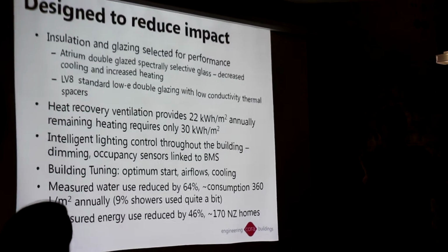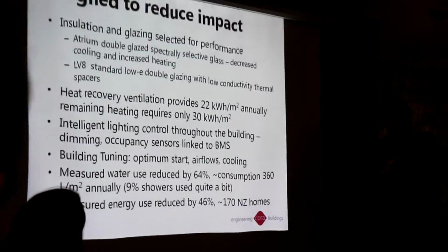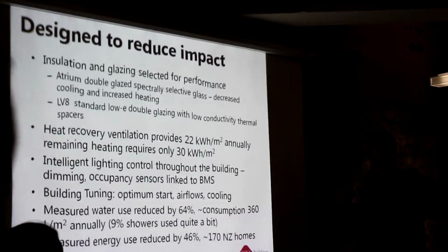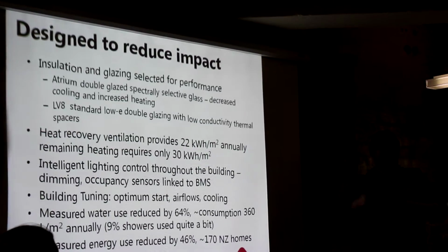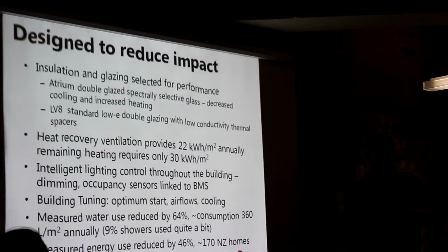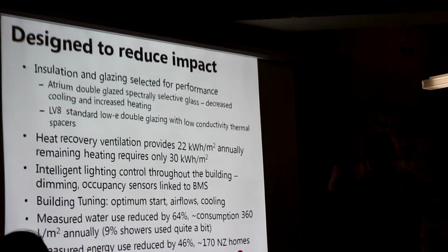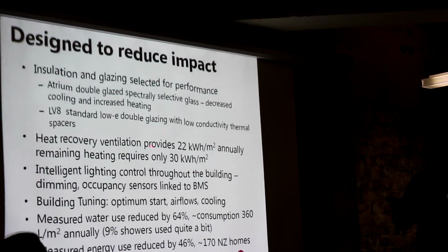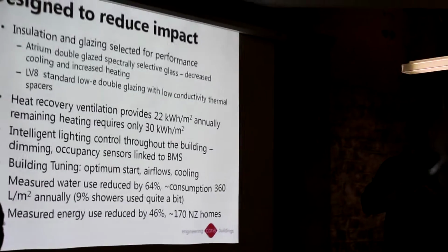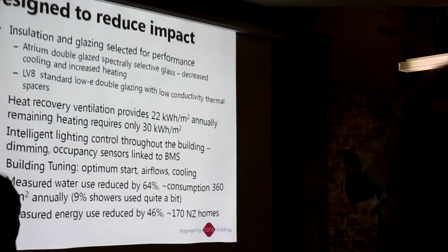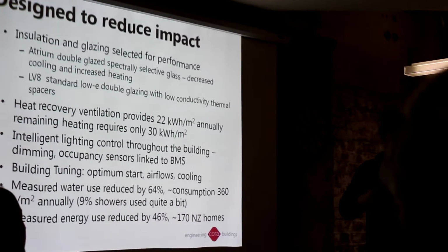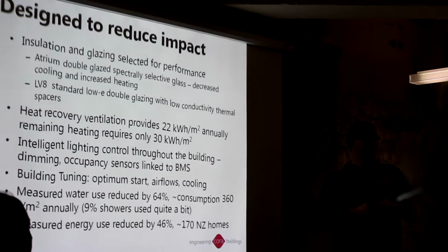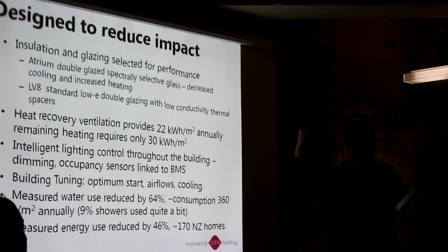When you're trying to design a low energy building, there's essentially two ways to think about energy flow through the building. Flow through the skin, which is either radiation or conduction, and then there's the intentional exchange of air. You don't want to breathe the same air inside the building, you want nice fresh air. So you want to recover as much energy as you can from that air you're exchanging and dumping out, so you don't have to pay for it. This building, because it's got heat recovered ventilation, recovers almost as much as it's putting into boilers, just from the incoming air. Which is why a lot of times there's just one boiler running, and sometimes that's not even needed, because the people inside are creating all the heat, and all that exhaust heat is preheating the incoming air.